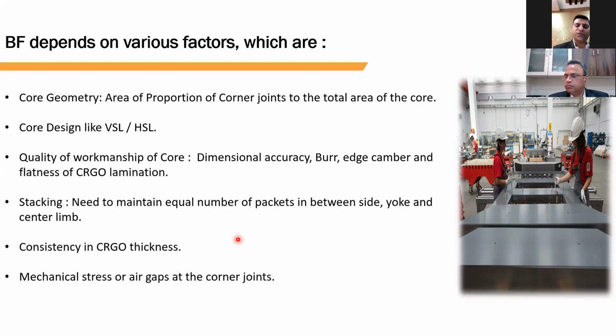So there should be proper control at the time of CRGO cutting. The operator needs to check if some pieces are missing or if any sequence is disturbed, and then stop the machine and place the required lamination at that particular area, so that the customer does not face any shortage or excess of lamination. That is a very important part. Yes, very important.